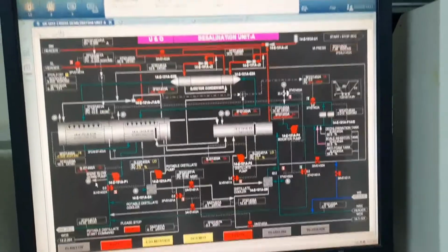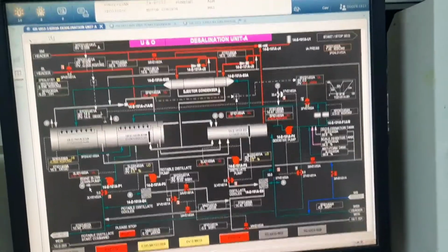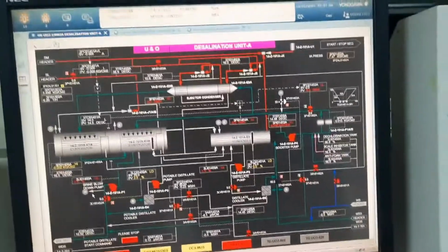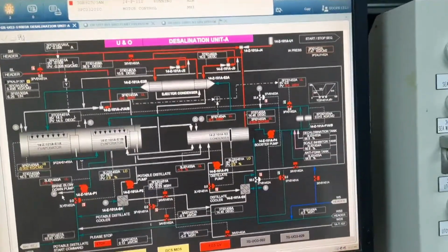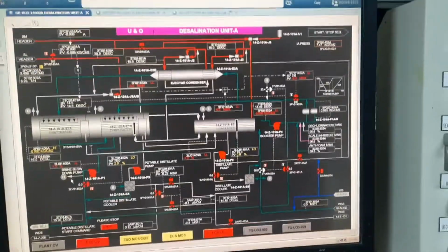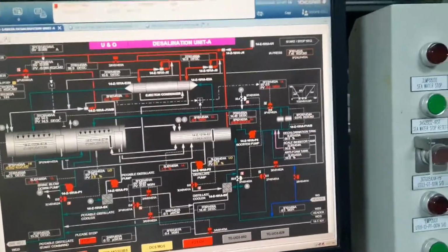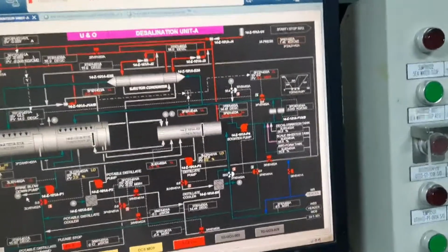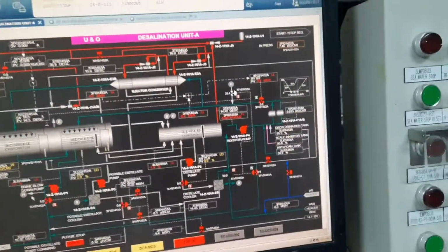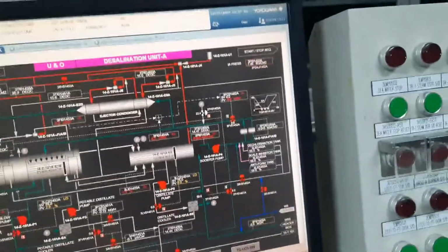And after dosing one batch, one container, we need to inform the laboratory for testing the pH, concentration, and calcium carbonate content, how much content is remaining. But I forgot to tell one thing: before doing this job, we need to inform the laboratory beforehand to take a service water sample first. We need to take the service water pH, how much. If you take one sample before, then you can easily calculate by how much it is reducing or increasing. Normally it will be reduced.